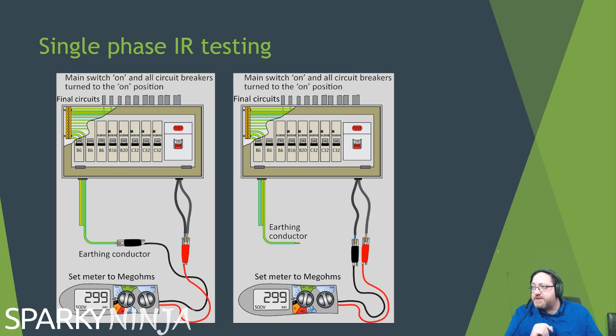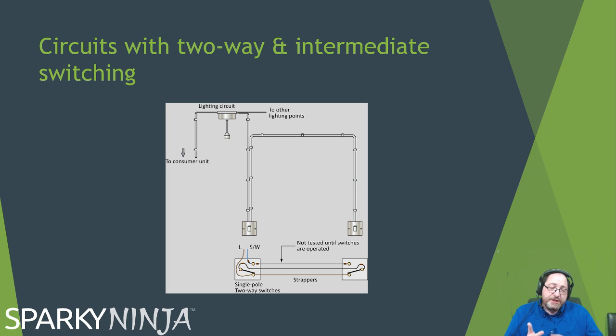Another thing with insulation resistance testing is your two-way switching, any intermediate switching. When we do a test to line and earth, and neutral if there's a neutral in the switches, we need to do it once, and then switch one switch to switch over to the other strapper, and then we need to repeat the test. Otherwise that line conductor that wasn't in circuit hasn't been tested.